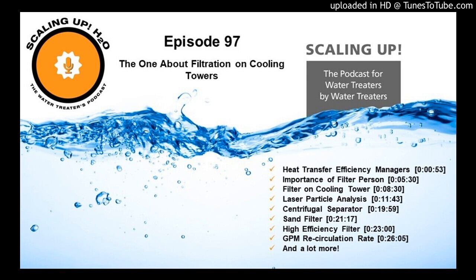That approach to dealing with whether or not I should buy a filter is the key to getting a filter purchased by a customer. That's where all the real big money is, heat transfer efficiency. So that's always where I head. So if you can convince the customer that they're paying for this, whether they realize it or not, the sooner they get something to take all these particles out so they don't settle and make their heat transfer equipment less efficient, they're going to start realizing the gain from that equipment.